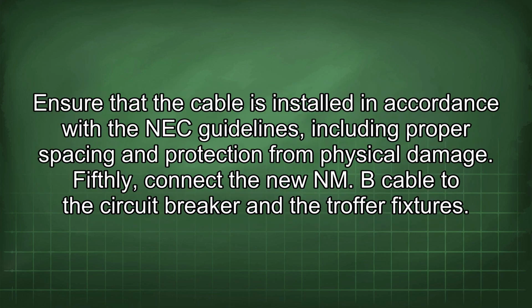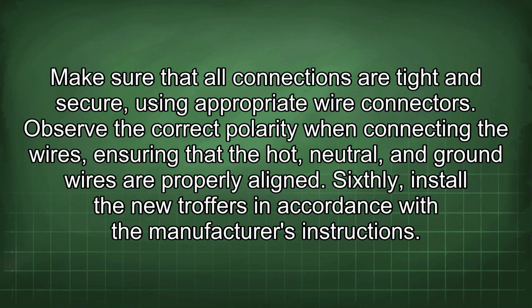Ensure that the cable is installed in accordance with the NEC guidelines, including proper spacing and protection from physical damage. Fifthly, connect the new NM cable to the circuit breaker and the troffer fixtures. Make sure that all connections are tight and secure, using appropriate wire connectors. Observe the correct polarity when connecting the wires, ensuring that the hot, neutral, and ground wires are properly aligned.